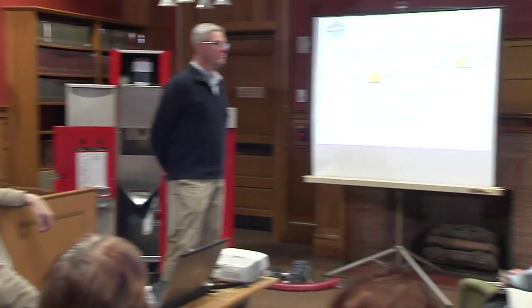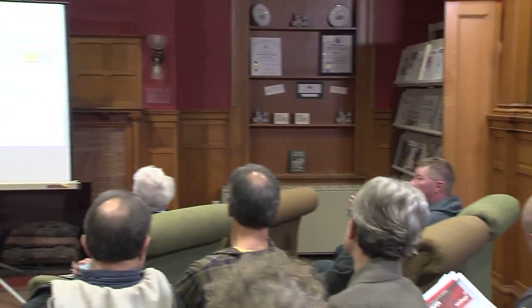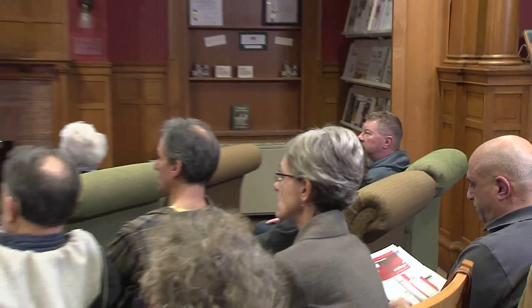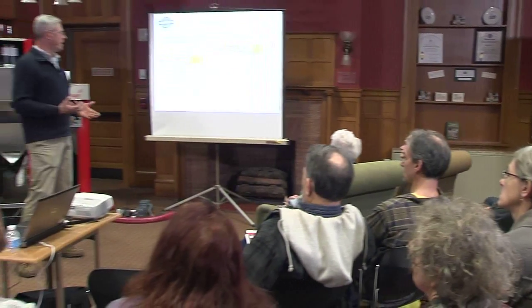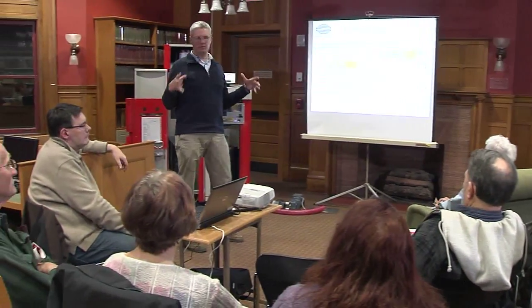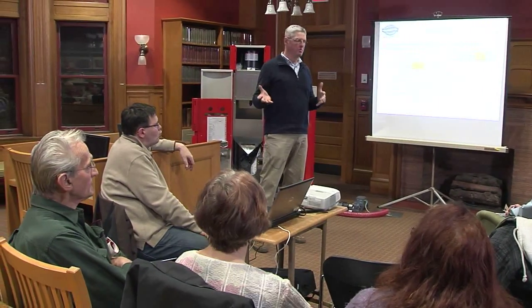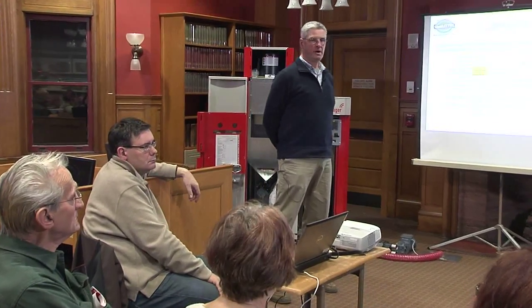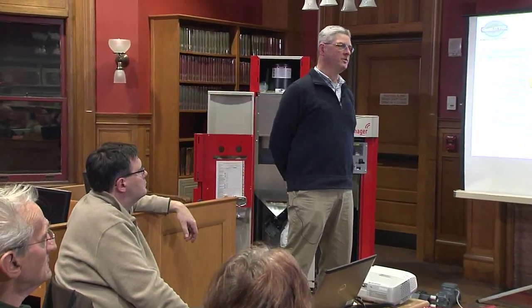Yeah, Mark? Someone asked earlier about makeup air. Our house is really tight, and the basement where the furnace is is pretty small. We go in and out of the basement maybe twice a day, and we've never had any issues with the furnace choking or smoking. Okay, just to repeat, somebody asked about outside air getting to that unit, and as Mark said, it's not a large space in their cellar where the boiler is, and they've had no problems. They don't open doors a whole lot. They've had no problems with air supply for this unit.